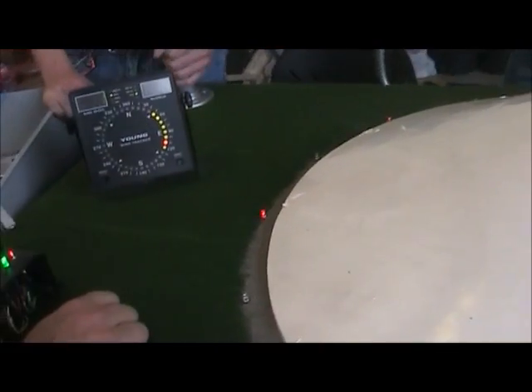And now, seeing as how if you have a gust of wind, you don't want your fans to be turning on and off. We have it stay in this stage for 30 minutes, but for the purpose of this display, we only have it going for 30 seconds. Gotcha. So we're not looking at on and off instantly. We're looking at kind of a steady. Because that would damage your fans and your motor starters over time. So each one of these fans, about how many horsepower would they be? 7.5 horsepower each.